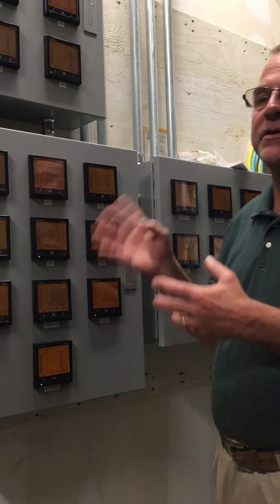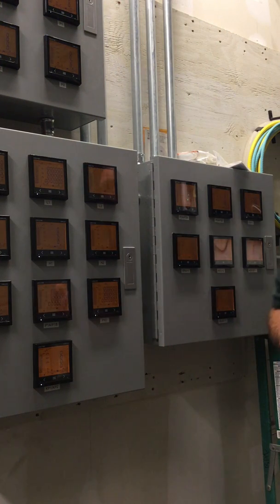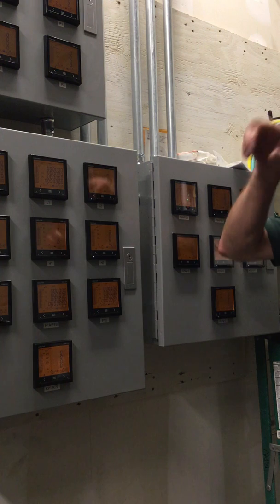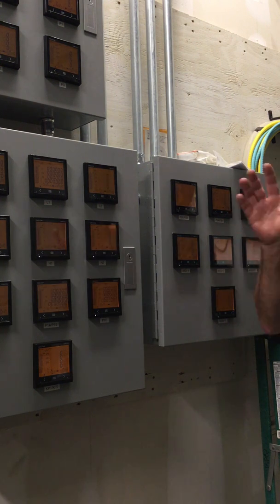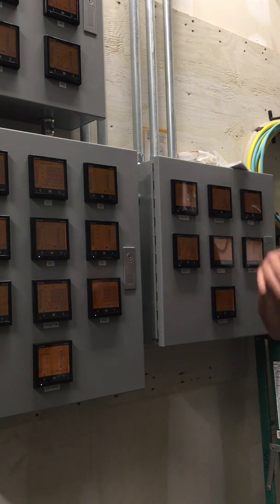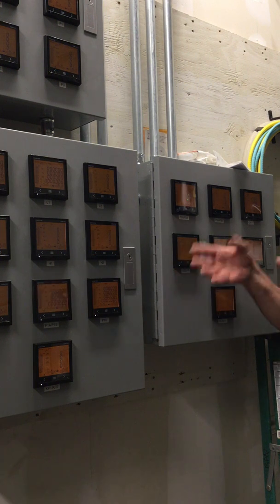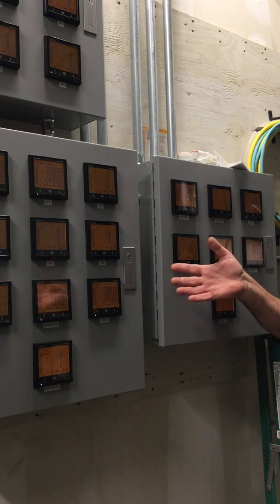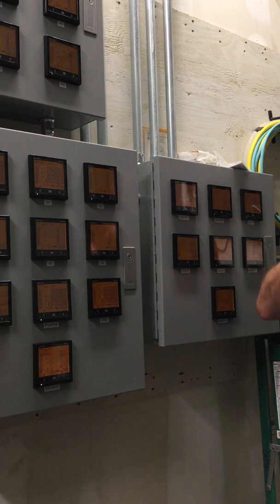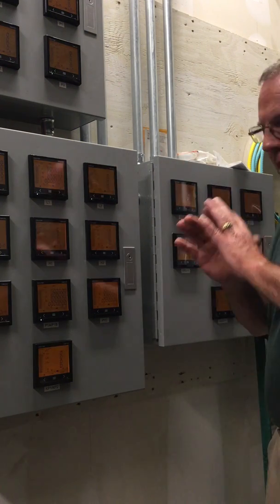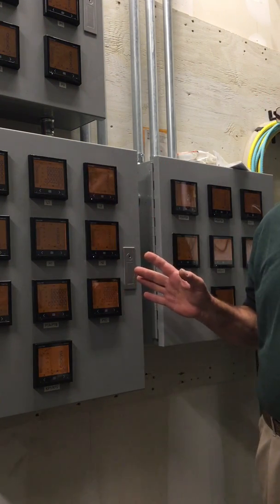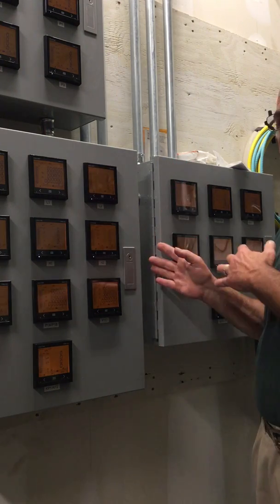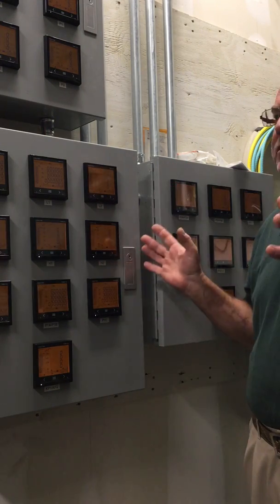So at that point, once they start ramping up usage, the kilowatt hours would be displayed. Also on the meters is kVAR hours, both leading and lagging. That's just where the amperage is ahead of voltage or behind voltage on the sine wave. Reactive power, wasted power, useless power, is power that's created by the load that the transformer has to generate in order to get the kilowatt hours through. It's just a function of the power. Nothing in this school is any different than anything else, including your house.